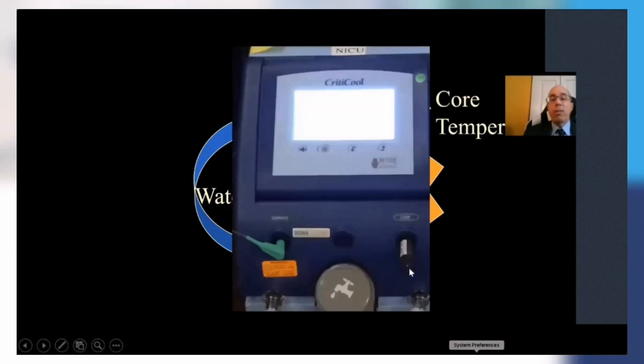So whatever core temperature the device is reading, about every 3 to 5 minutes we would match that core temperature in the machine by turning this dial. And then the CritiCool would make any adjustments if the core temperature was either below or above the targeted temperature, and it would either cool or heat the water to bring the baby within that desired temperature range.